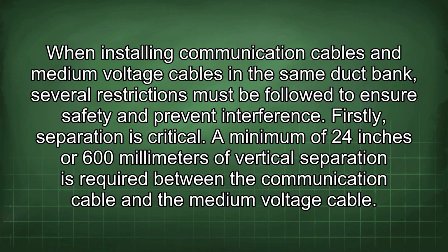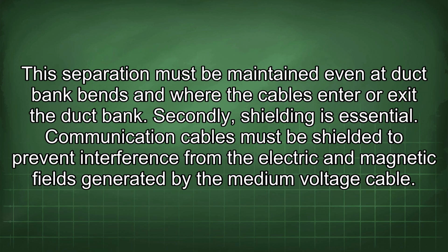When installing communication cables and medium voltage cables in the same duct bank, several restrictions must be followed to ensure safety and prevent interference. Firstly, separation is critical. A minimum of 24 inches or 600 millimeters of vertical separation is required between the communication cable and the medium voltage cable. This separation must be maintained even at duct bank bends and where the cables enter or exit the duct bank.